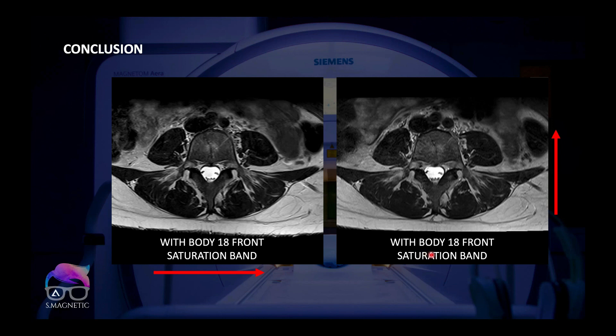If you want to stay with the AP direction, use it with the saturation band because of the respiratory artifacts, and remember to turn on the front coil elements to get more homogeneous signal intensity throughout the image.